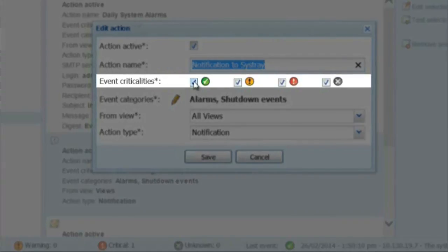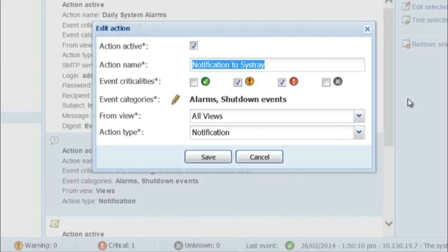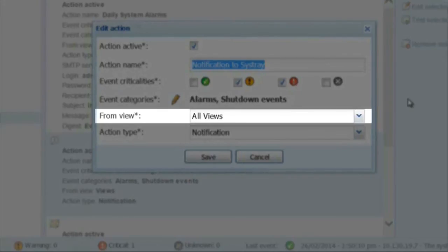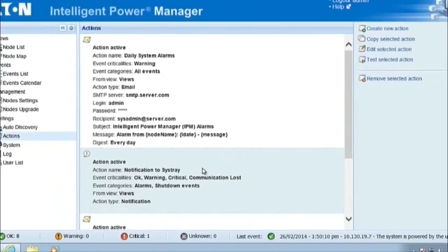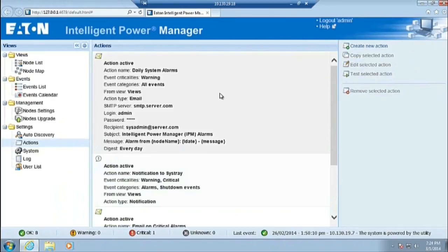Event Criticalities: only select the yellow exclamation icon and the red exclamation icon boxes. From View: select all views in order to encompass all areas for alerts. Action Type: select Notification. Click Save to continue. Please note that if you have an unmonitored server installation, you will need to uncheck the box labeled Action Active. If the installation is unmonitored, no one would see the notifications, so they will not need to remain active.